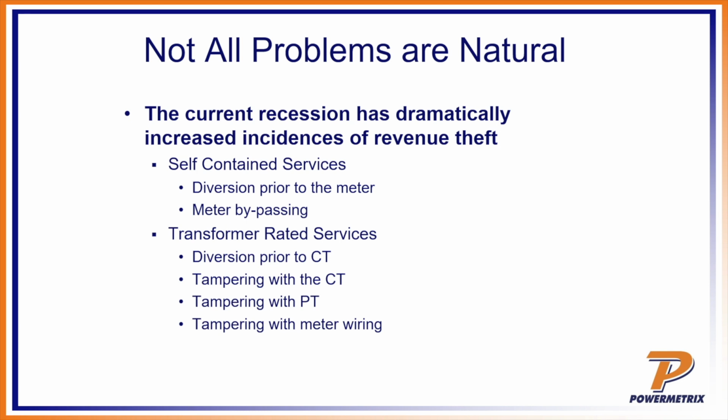Well, nobody knew about that. They knew that the numbers were coming back to the office, and the bill was decreased, and somebody said, this needs to get checked out. This doesn't look right. They went to the site. Everything at the meter looked right. Somebody finally gets in a bucket or a ladder, and they finally found there were extra turns, and nobody knew about it. They removed those turns. They made everything right. They removed the extra wiring, and everything came back into order again.